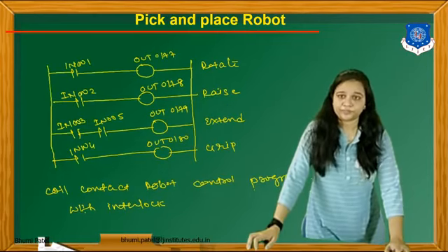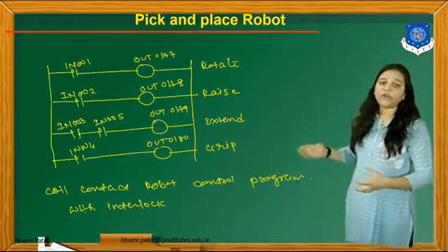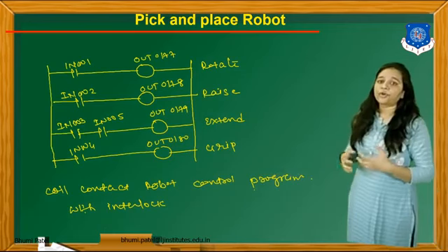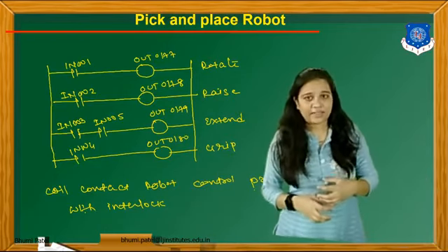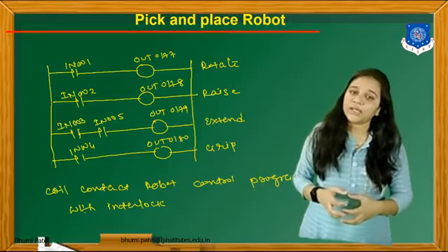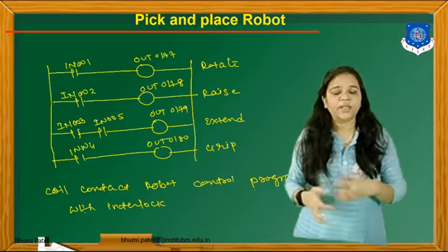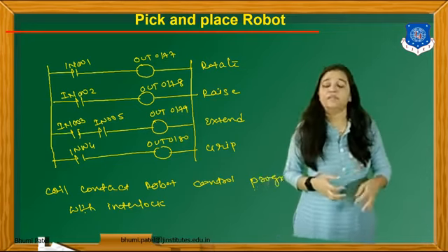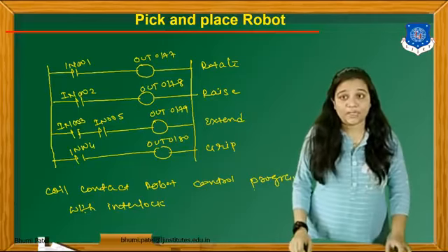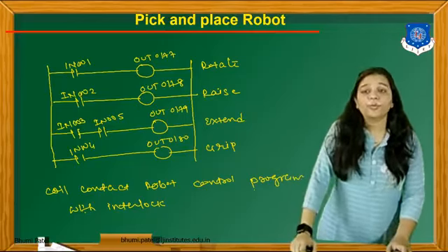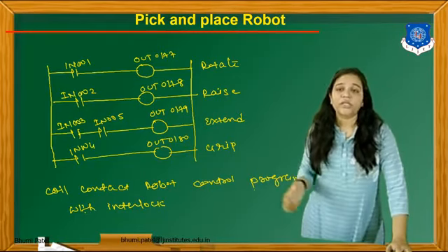So this is my actual ladder program with the coil contact robot control program with the interlock. If the rotate function is there, the raise, extend and gripping parts are compulsorily off. If the gripping part is there, we have to compulsorily interlock with the rotate, raise and extend parts. So simply we have to put the interlock in every rung.